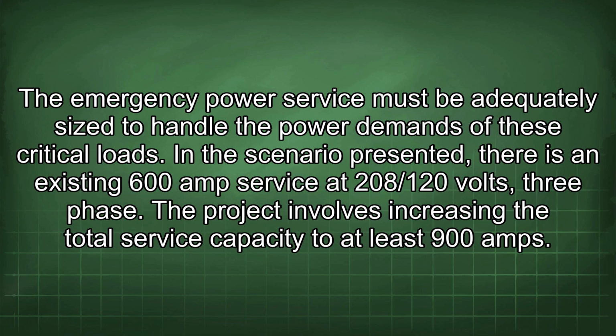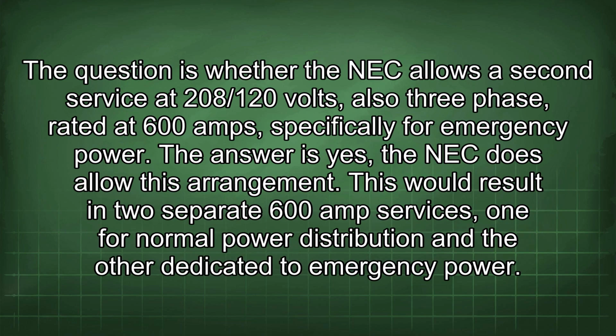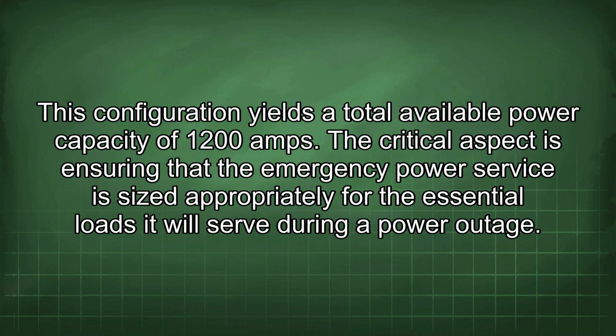In the scenario presented, there is an existing 600 amp service at 208/120 volts, 3-phase. The project involves increasing the total service capacity to at least 900 amps. The question is whether the NEC allows a second service at 208/120 volts, also 3-phase, rated at 600 amps specifically for emergency power. The answer is yes, the NEC does allow this arrangement. This would result in two separate 600 amp services, one for normal power distribution and the other dedicated to emergency power. This configuration yields a total available power capacity of 1200 amps.